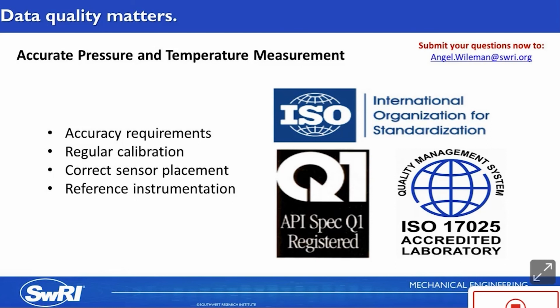We typically have one just downstream of our high pressure pump as a reference measurement. This will help give you an indication if something is not scaled correctly, if an instrument is damaged, or if noise sources in the lab are interfering with the signal. It's easier to take steps to resolve these issues early on instead of midway through the test sequence, so you don't have to repeat cycles.